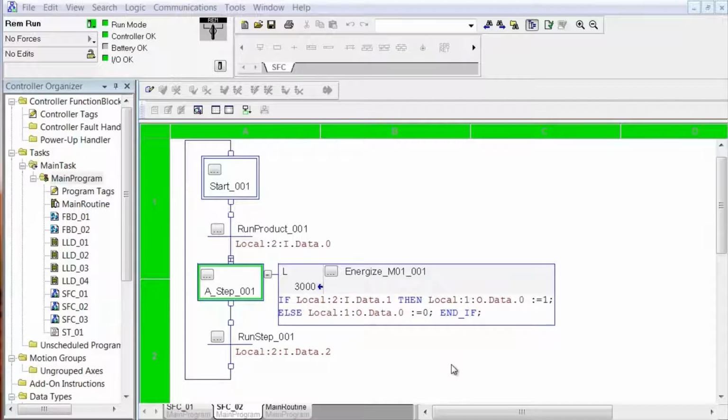It's time limited. Then I had you press and release input 1 repeatedly. Okay, well, nothing's happening. I'm doing it. Nothing's happening. Why? Because that action is now not active. The step is active, but the action is not. Okay, press and release input 2. This sequences the SFC back to the start step.